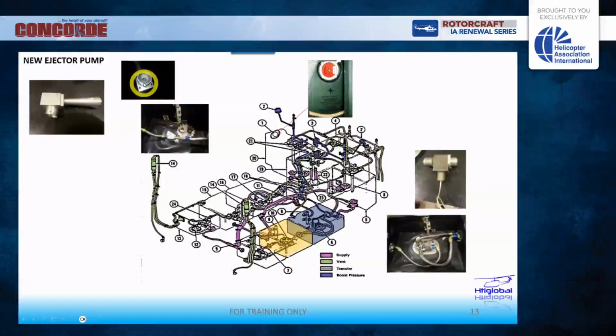This is a check valve, and what happened is many years back, I think over 25 years ago, they had some issues, what's called a reflux. When we start flying the helicopter, many things happen. Even the sequence of burning the fuel reaches a point where the mid cells and forward cell are going to be empty. During that time, if you have a reflux of fuel going back to the mid cells, that fuel gets trapped. That's dangerous because it limits your range. If you fly offshore, that can cause a very bad situation where you run out of fuel before reaching your platform. So Bell is always trying to improve the system, and this is a good option, a technical bulletin where you change the ejector pump.